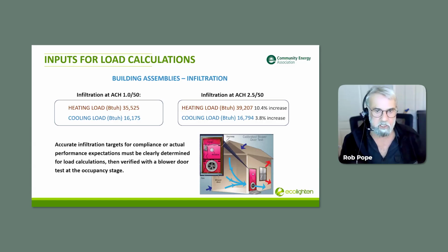So that's the condition the house is in. If the homeowner just wants the heating system changed out with no plans to do anything else to the house, that's what you're going to work with, right? And so that's what you design to. But it's important to understand that in a lot of cases, unless it's an emergency, the homeowner is changing the heating/cooling system as part of a bigger plan, and they are interrelated and interdependent. If that's the case, then we have to set an ACH target, an infiltration target—we're going to do some weather stripping, some sealing here and there, put in better windows, whatever. Somebody's going to make an assumption. The target infiltration is going to be a guess. It might be a good guess, but it's still a guess, because you don't know for sure.